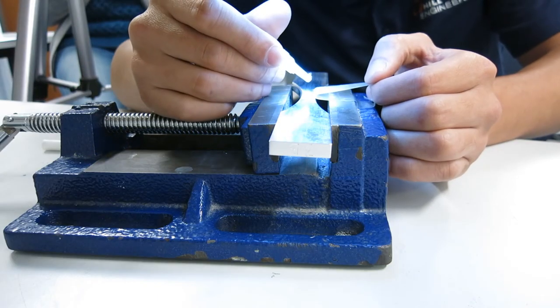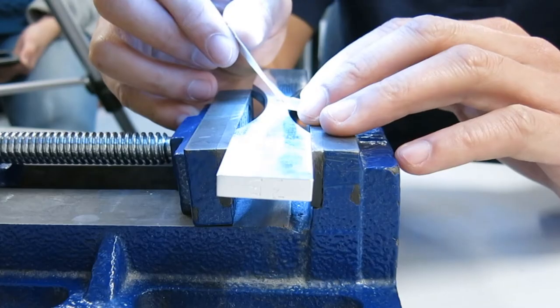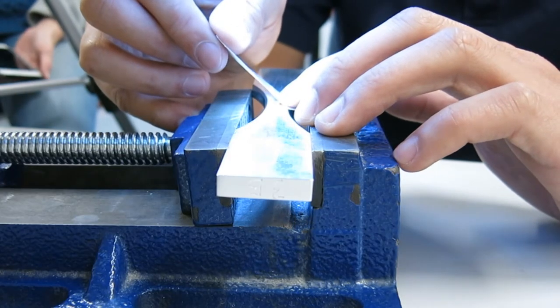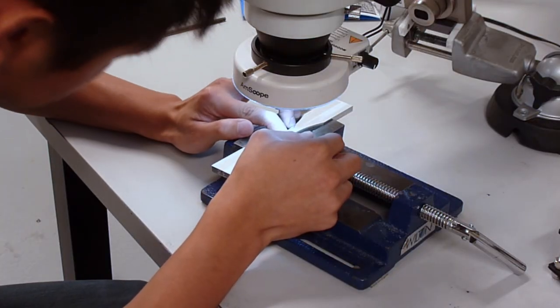Next, place one drop of adhesive at the junction of the tape and specimen. Holding the tape taut, slide your finger over the gauge assembly, sticking the gauge down to the surface.